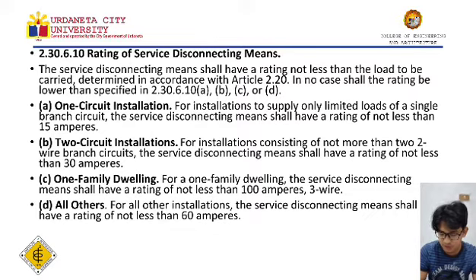2 circuit installations naman po, for installations consisting of not more than 2 wire branch circuits, the service disconnecting means shall have a rating of not less than 30 amperes. So, para sa mga installation na binubuo ng hindi higit sa 2-wire branch, ang service disconnecting means nito ay hindi dapat baba sa 30 amperes.